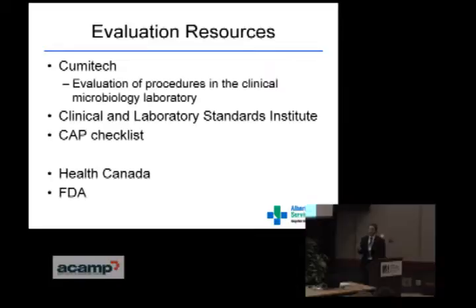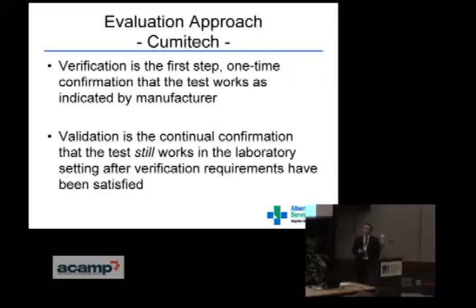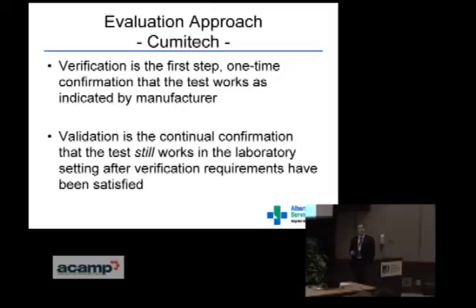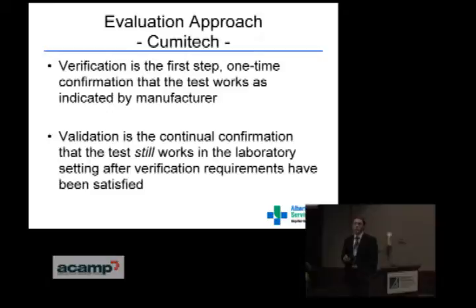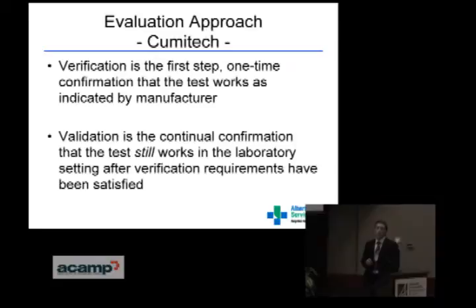As a matter of establishing framework, drawing from the Cumitech publication, for a commercially available assay to be implemented into clinical service, we first must do a verification. As defined, this is simply the first-step, one-time confirmation that the test works as indicated in the product insert as deemed by the manufacturer. In comparison, a validation is that continual confirmation after verification that the test still works and continues to work over the duration of its application within the laboratory setting.